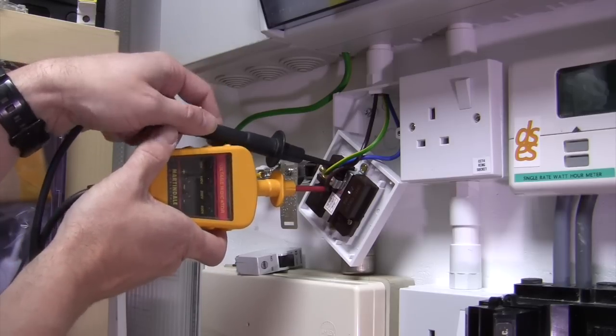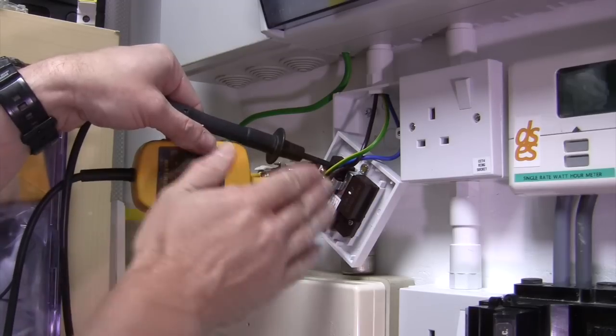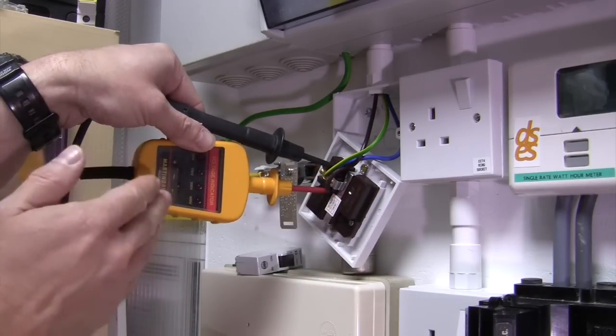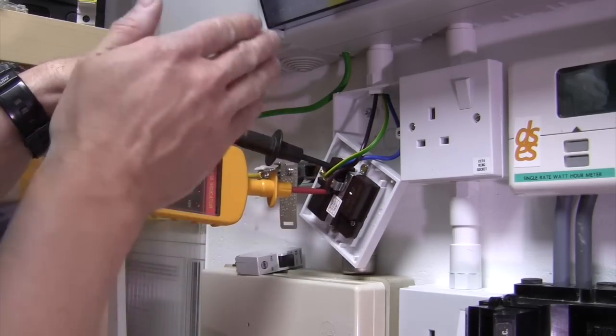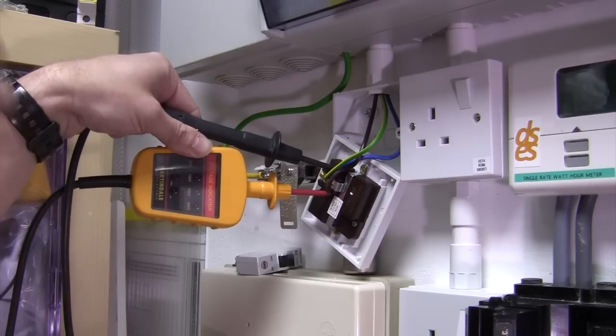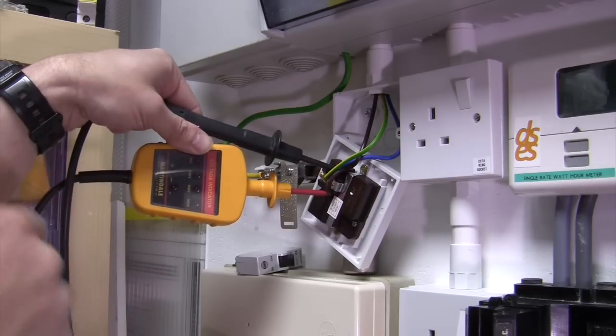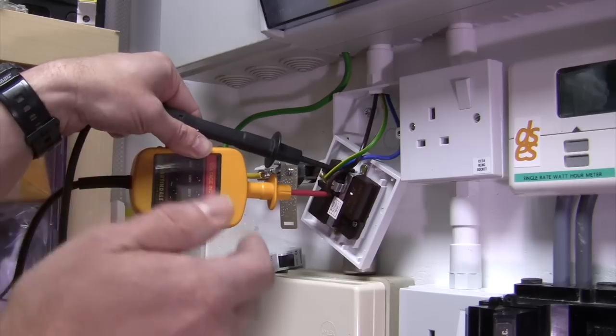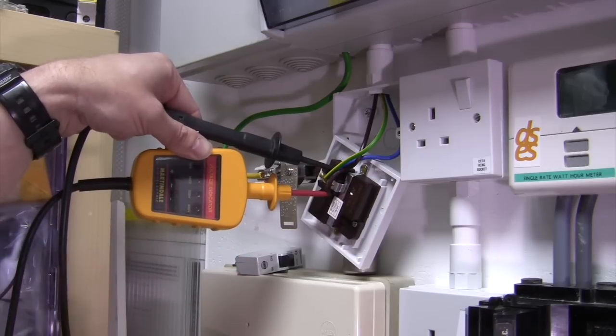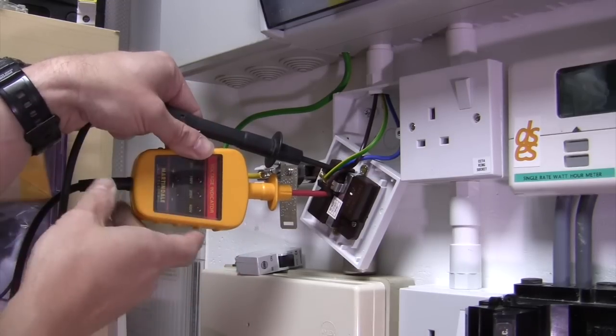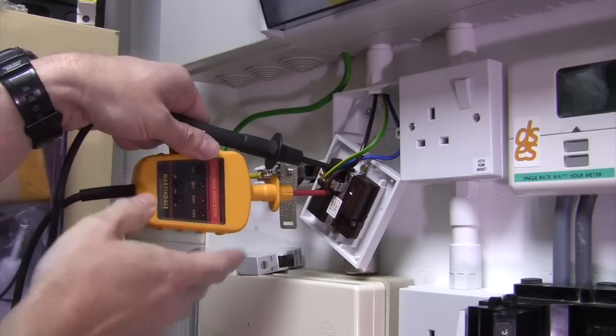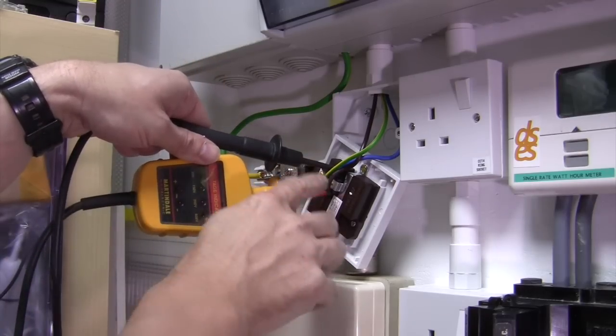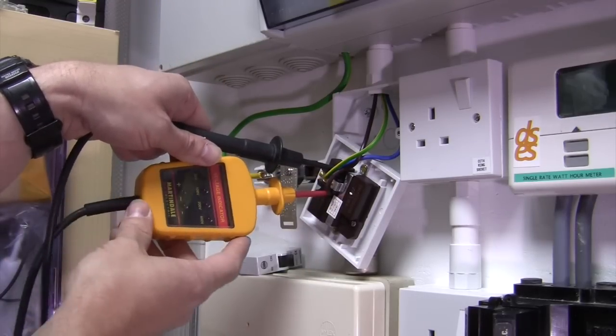However, what if it's not dead? What if the line is still live and the voltage indicator isn't showing anything because it's the neutral that's been disconnected? Maybe the neutral's broken, or maybe it's been wired incorrectly upstream and a single pole isolator has switched off the neutral instead of the line. In that sort of circumstance, the voltage indicator would indicate that it's safe when in fact it's not, and if I touch that I could get zapped.